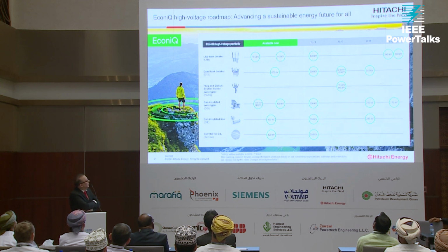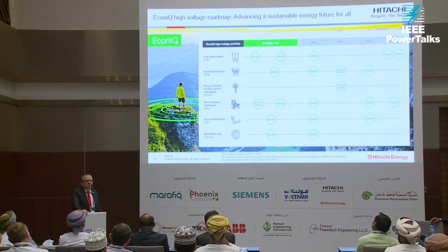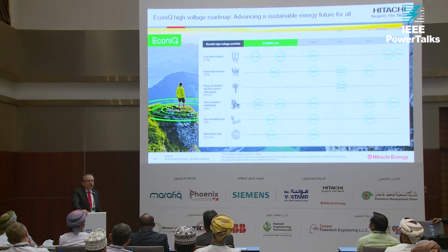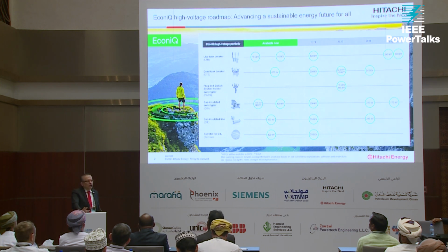The second-to-last line is the gas-insulated line. Why is it so important? Especially at 400 kV, many substations might have kilometers of GIB. On average, a normal 400 kV substation has about 40 meters of GIB per bay. Consider that in a substation with 20 to 25 bays, it adds up to around 1 kilometer. In some projects I've come across, they use up to 10 kilometers of GIB. So GIB is also important.